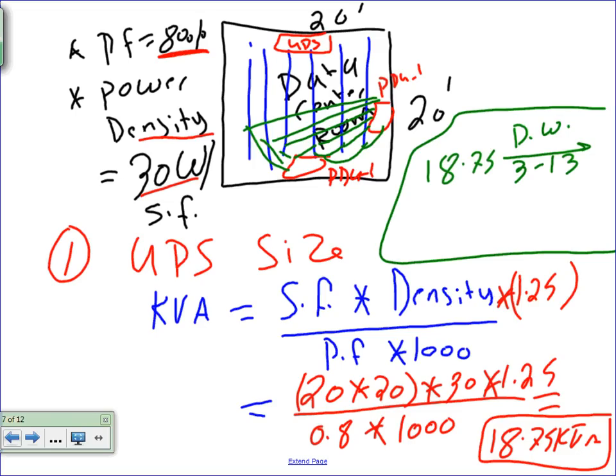So the smallest that I can buy, from that sheet, did you guys get the sheet? Is 40, right? Smallest that I can buy is 40. So I have a 40 kVA. The smallest I can buy is 40. At least this size. I'm sure there's other sizes, but for the sake of the calculation, these are the numbers we're going to use. If you guys go to manufacturer of UPS, they have a list of all the sizes, technical sizes that they have. And from there you can find the actual size. Okay, so I size my 40 kVA. Any question about the 40 kVA?